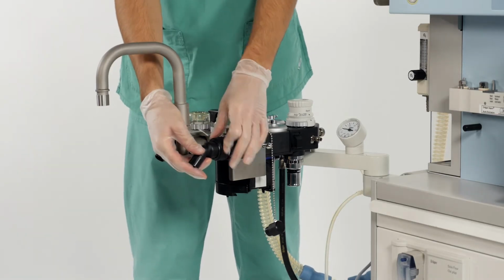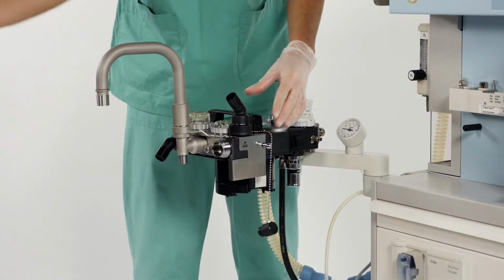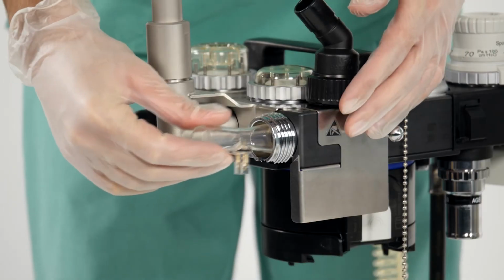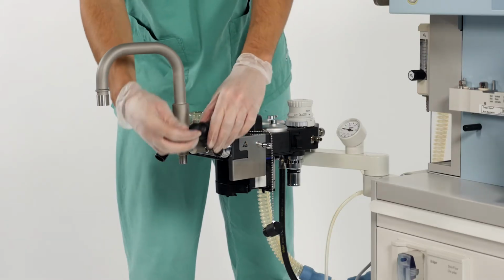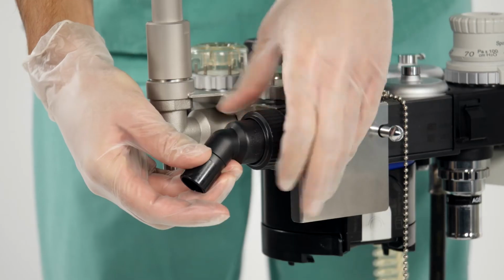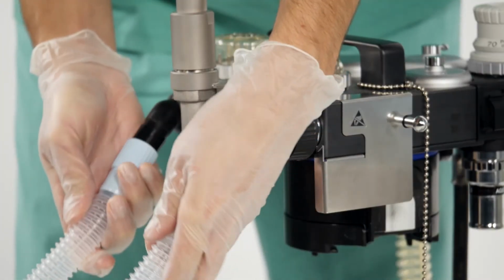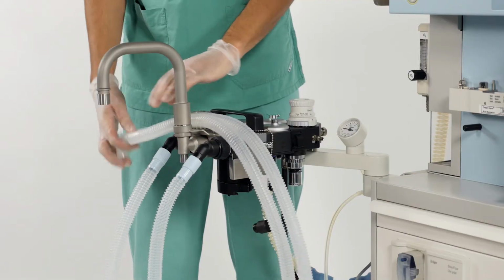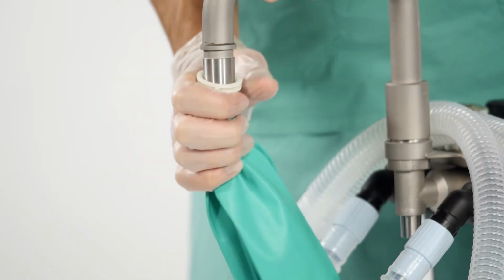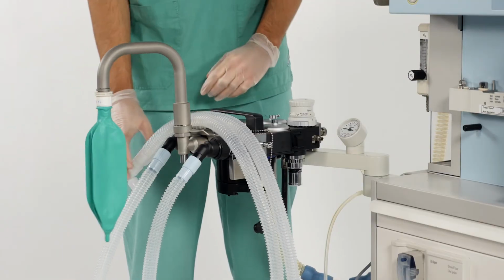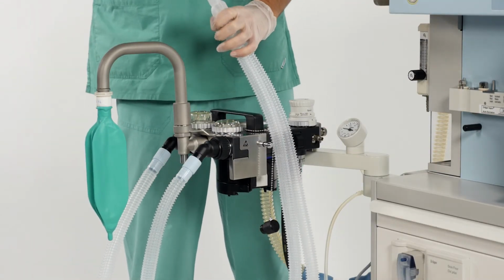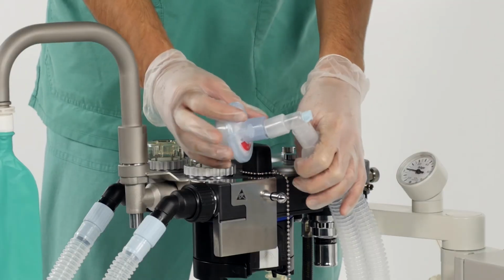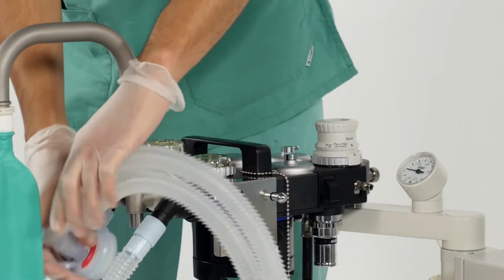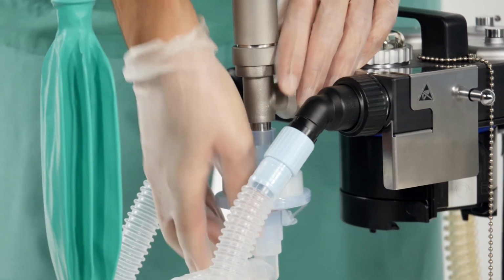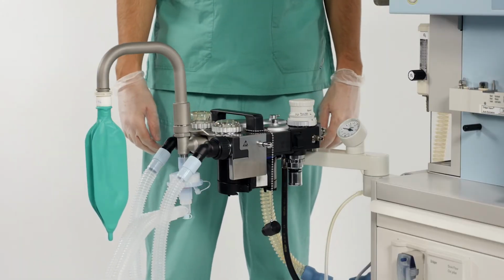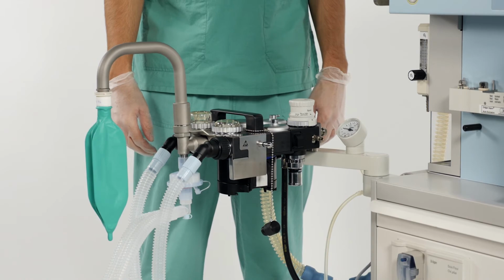To insert the flow sensor, unscrew and remove the expiratory port from the breathing system. Insert the flow sensor and reinstall the expiratory port. Connect the patient breathing hoses and the manual breathing bag to the inspiratory, expiratory and bag hose ports on the COSY. All filters that will be used during operation should be installed as well, in order to include them into the self-test. In this case, we will use a filter on the Y-piece for demonstration. Place the filter on the park position on the back port of the COSY.